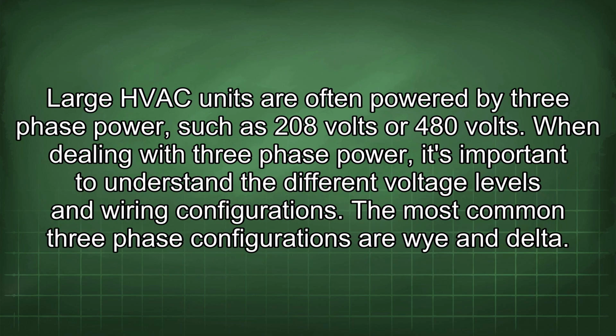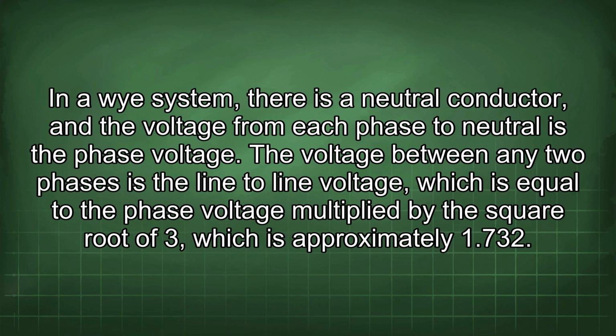Large HVAC units are often powered by three-phase power, such as 208 volts or 480 volts. When dealing with three-phase power, it's important to understand the different voltage levels and wiring configurations. The most common three-phase configurations are Y and delta. In a Y system, there is a neutral conductor, and the voltage from each phase to neutral is the phase voltage.